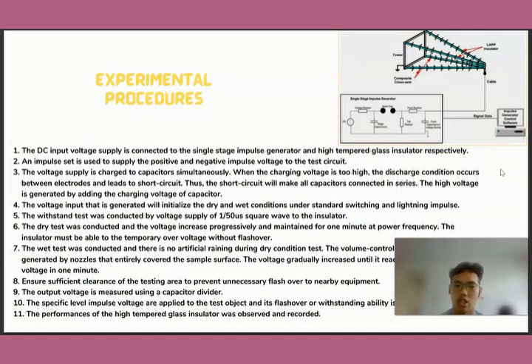Thus, the short circuit will make all the capacitors connected in series. The high voltage is generated by adding the charging voltages of the capacitors. Fourth, the voltage input generator will initialize the dry and wet conditions under the standard switching and lightning pulse test. Fifth, the test is conducted by supplying a 1/50 microsecond square wave voltage to the insulator.